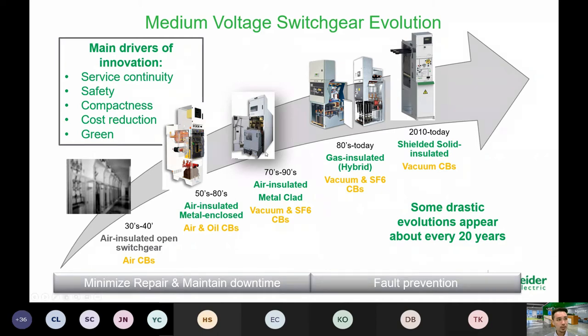That is why, in terms of safety and continuity, the designers came out with a much more robust and safer feature, where we house the circuit breaker in a tank that is fully sealed. In a way, that eliminates the requirement of drawing out the circuit breaker. So there are certain benefits moving into gas insulated technology. One of the key factors is that you minimize downtime, because maintenance is largely reduced. Of course, going into 2010, there is also the IS series, the shielded solid insulated switchgear, which has been introduced into the market as well. Later on, I will also do a quick sharing on some of this series.